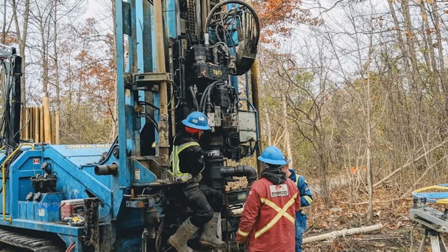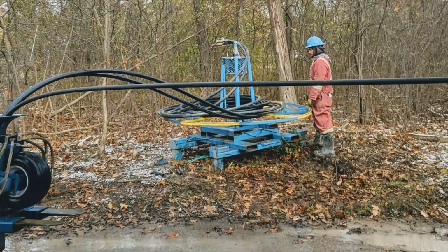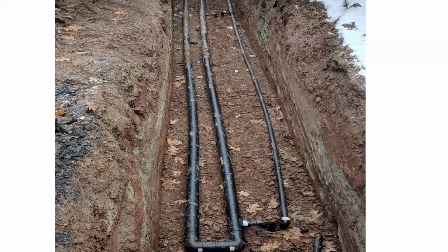The whole system relies on being able to extract either heat or cold from that water source. In our case, we're extracting between 4 and 5 degrees for heating purposes. We're just about to go into the cooling season, and I don't think it will be too different — we'll be extracting that amount of cool. We're circulating water through, putting it back into the earth, and it comes back into the building again after going through 1.5 miles of piping at a constant 52.5 degrees. So the technology is working exactly as the engineers had said it would.